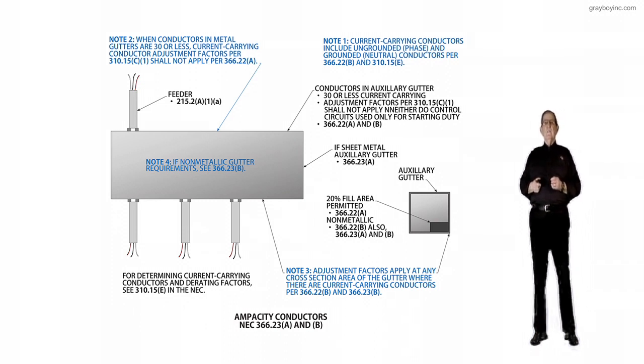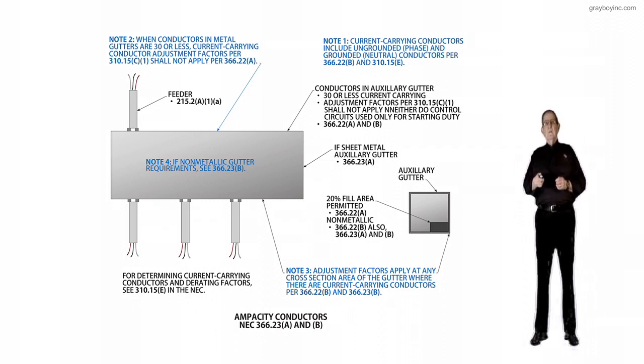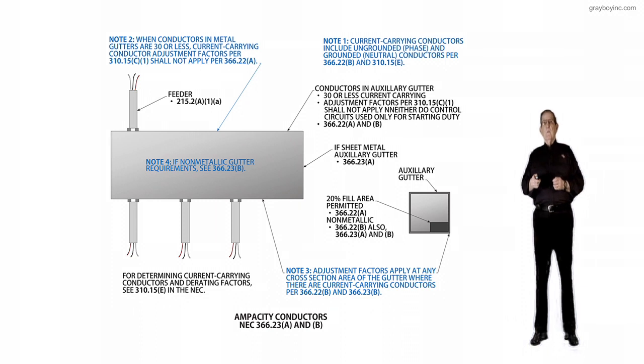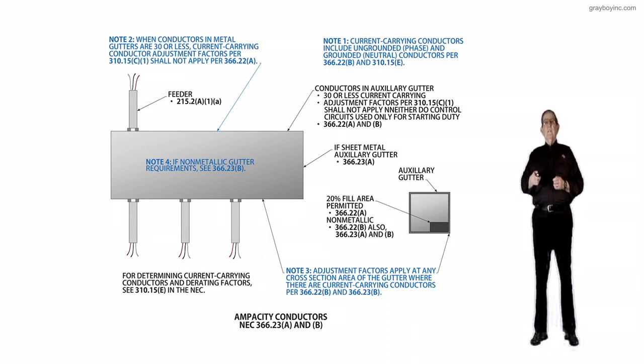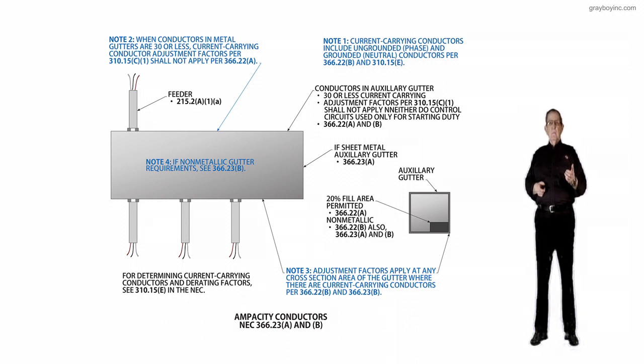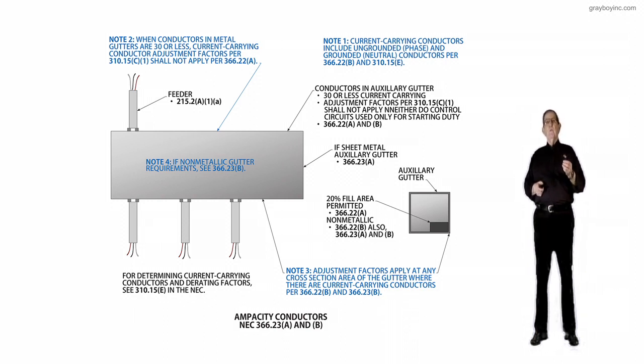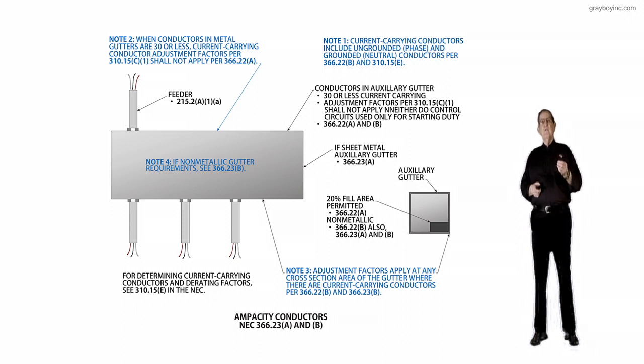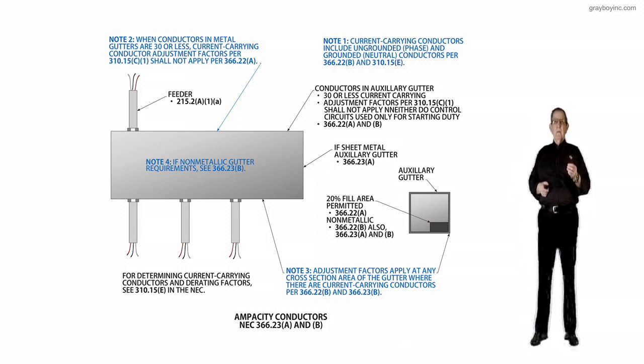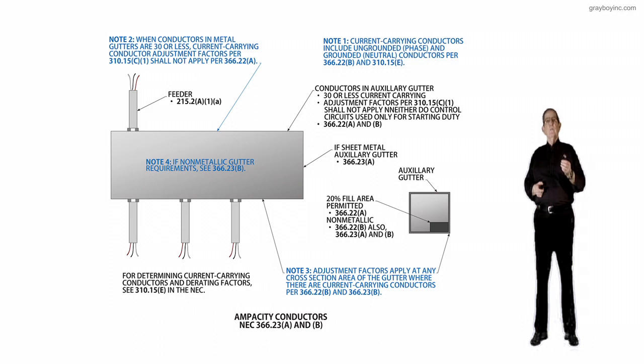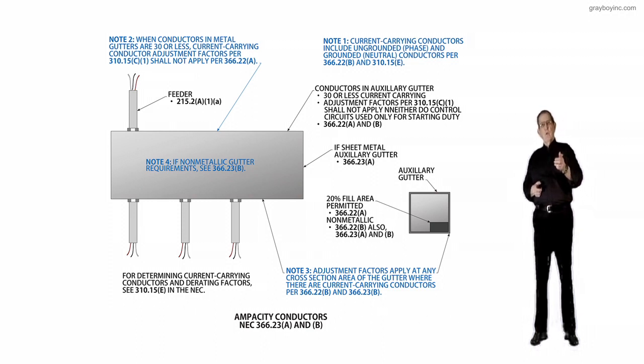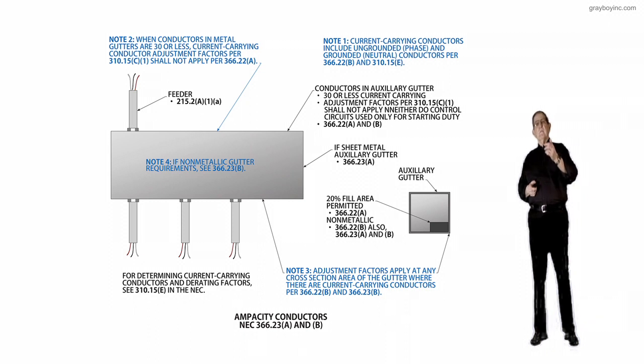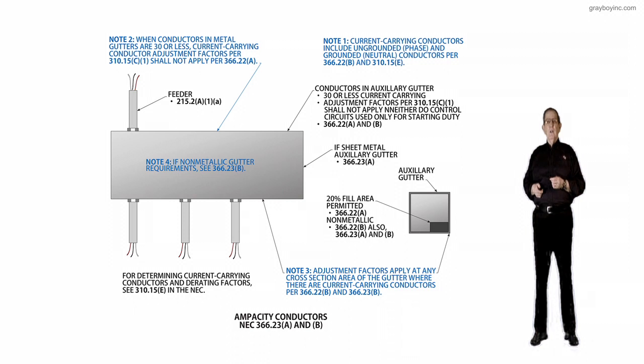Notice, if I want to determine the size of a bus bar or bus bars that would be installed inside this auxiliary gutter, I could look at 366.23A, and if I had a quarter by four-inch bus bar, multiply that times 1,000, and that would give you the amount of amps you could put on that bus bar based on it being copper. If it was aluminum and it was a quarter by four, that would be times 700, and that would give it to you for aluminum.